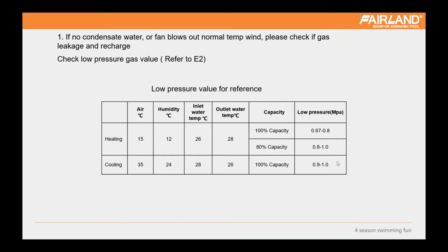So we will check if the condensed water is normal. Here we also share one thing: the customer will sometimes consider condensed water to be a leakage. So we will suggest the customer put the heat pump on standby, shut down the heat pump and just run the circulation pump, to check if water is still coming out from the bottom of the heat pump. If yes, that really means something, maybe a leakage on the heat exchanger. But if there is no leakage, that means the water is just condensed water, even if it seems a little much.